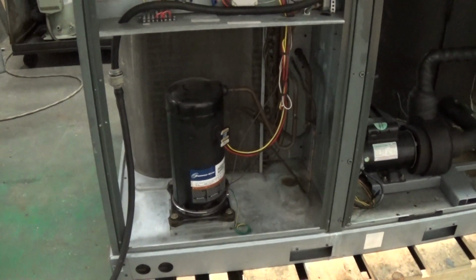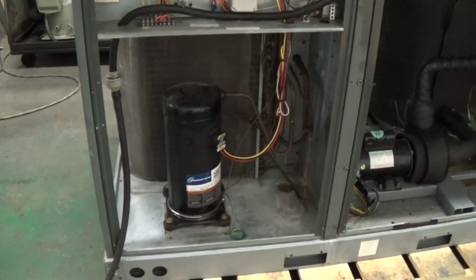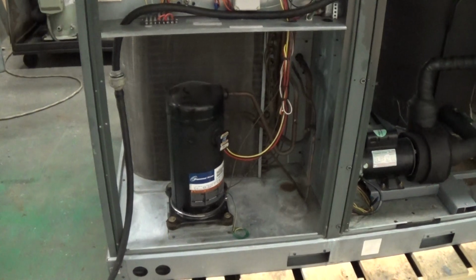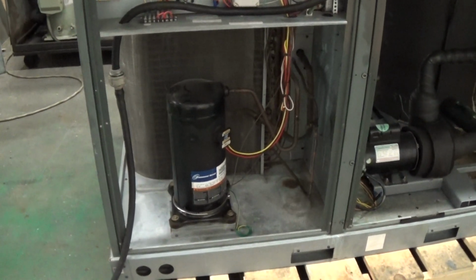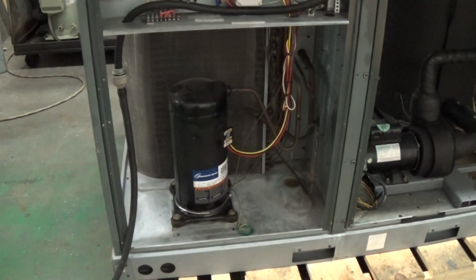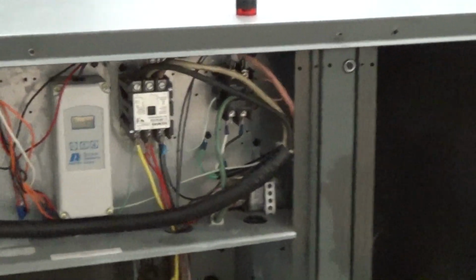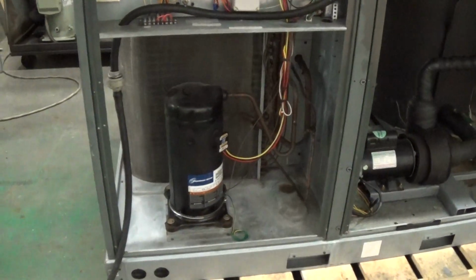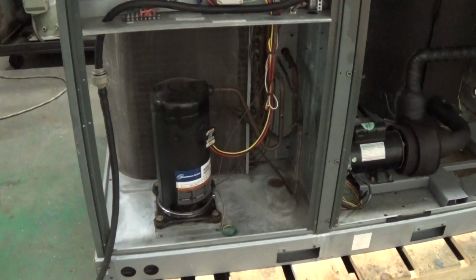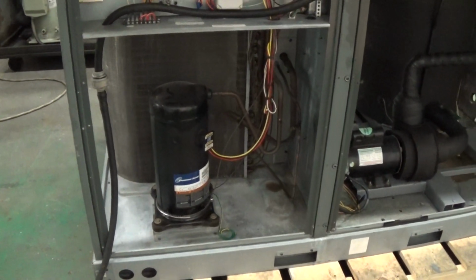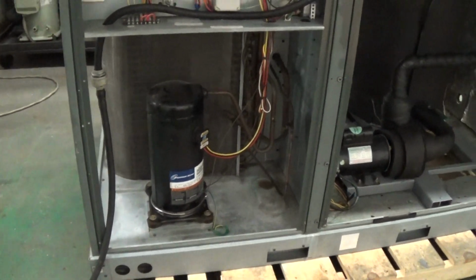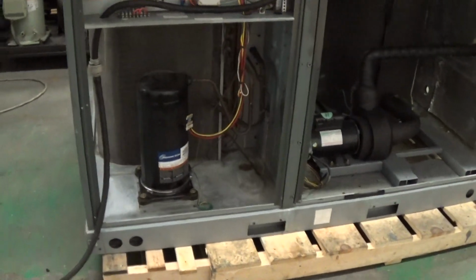But what I like to do is start the unit up, let the compressor kick on, listen to it, monitor it for a couple seconds, disconnect the power, change any 2 power leads there, do the same thing over again. And the quieter of those 2 modes when the compressor is running is the right rotation. That's the most simplistic layman's terms how to do it.